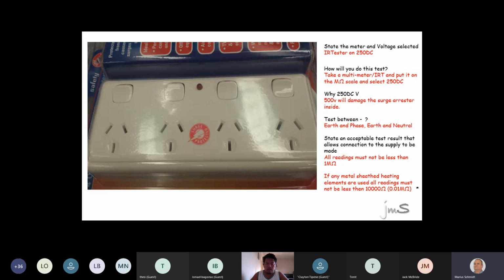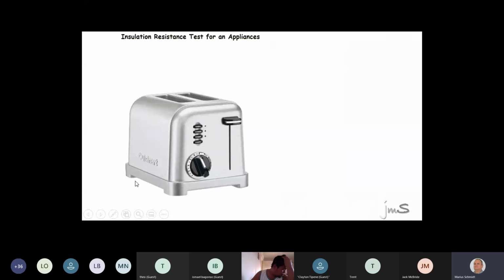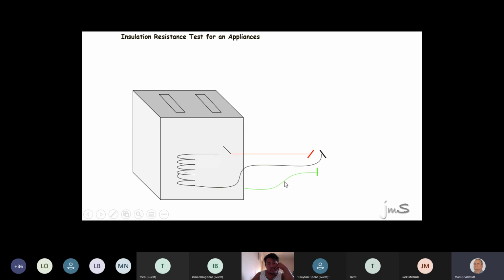Yes, correct. Now guys, never between phase and neutral. Earth to phase, earth to neutral. If I give you a kettle, you first check the earth, then you test earth to phase, earth to neutral. Happy? Now guys, this insulation resistance test I'm talking about, do you all agree we do it while the installation is dead? Right, cool. When I give you a toaster and you look inside, do you agree you're going to test between earth and phase, earth and neutral?